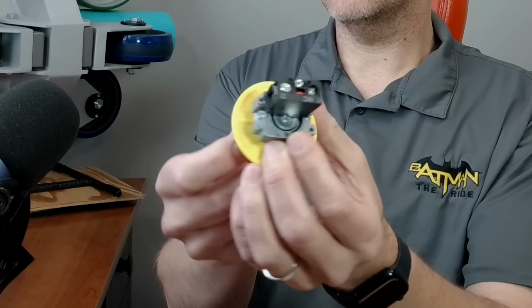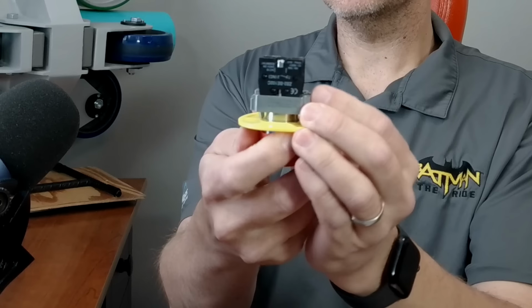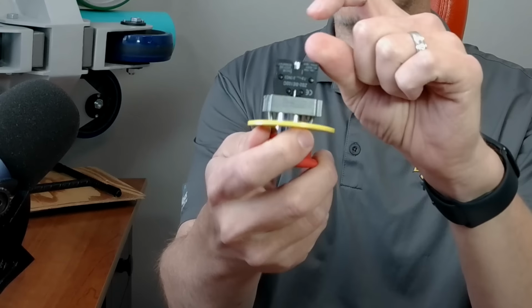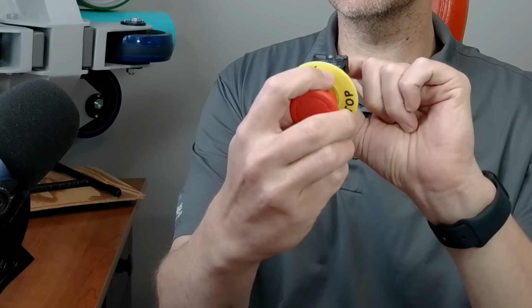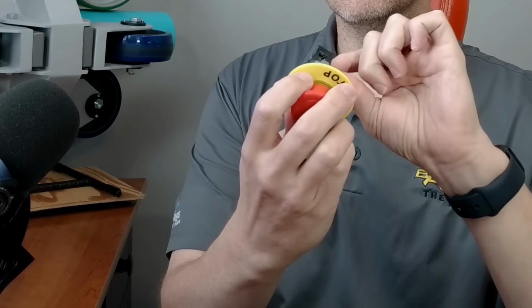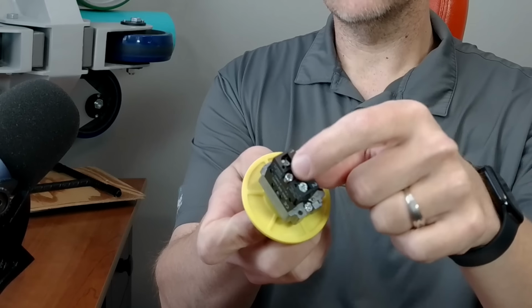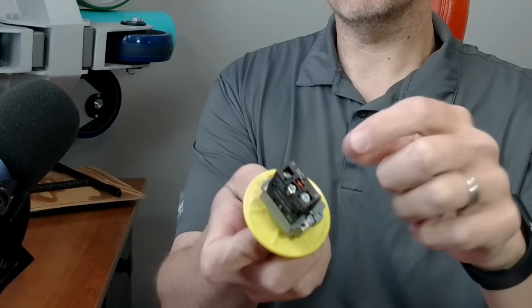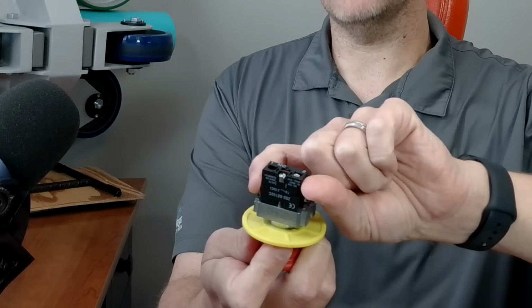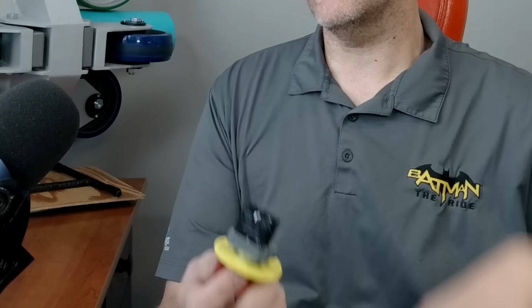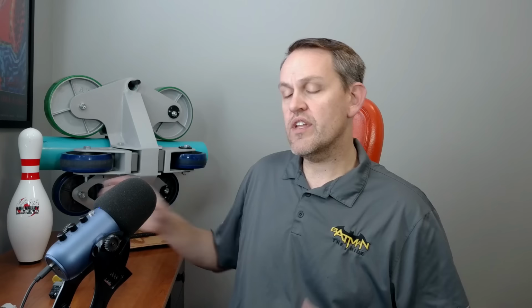Well, I could take another one of these contact blocks and I can essentially stack it on top of this one and put two little screws in it to hold it. And then, see right there, that screw? That screw allows another screw to go down on top of it. So I could just start taking these contact blocks and stacking them up, as many as I want to. That is essentially an emergency stop relay too. The relay has all sorts of contacts just stacked on top of them. They're really big relays, but they feed power to almost everything in the ride.